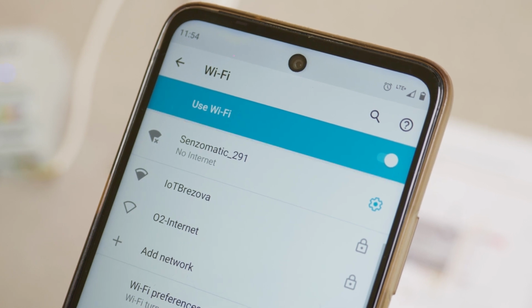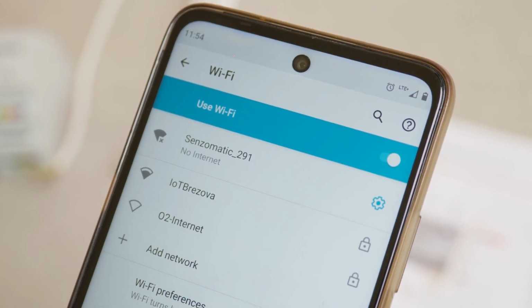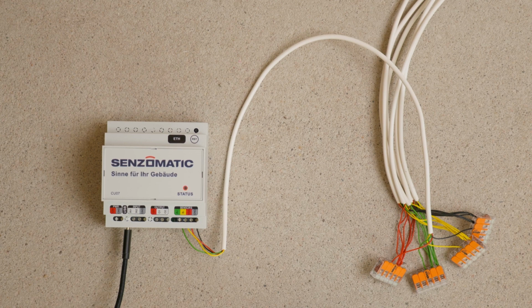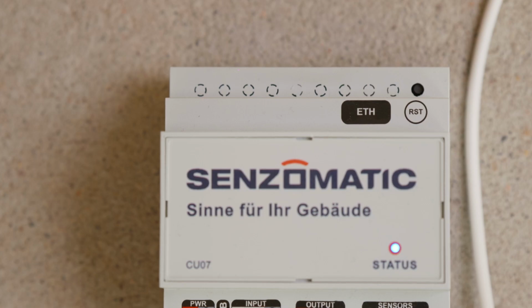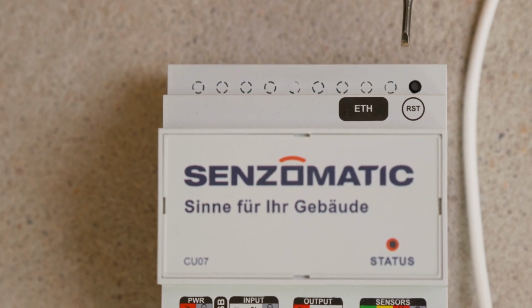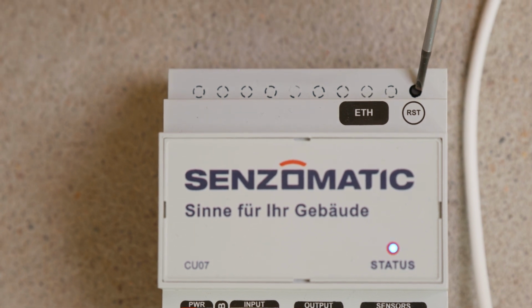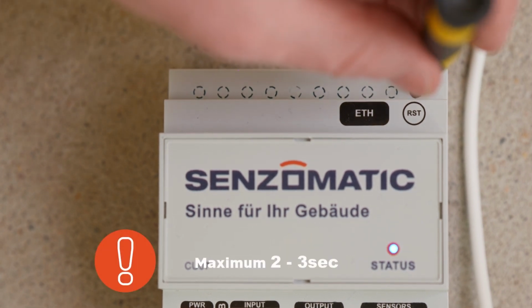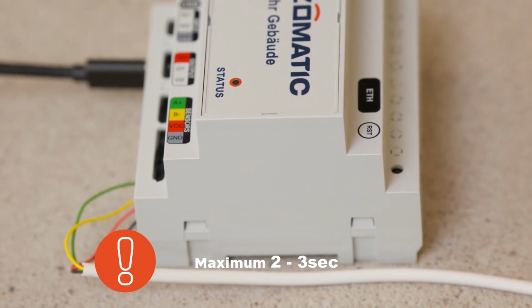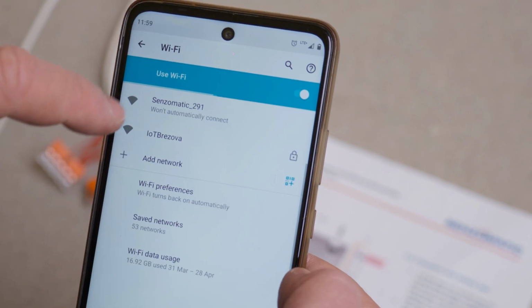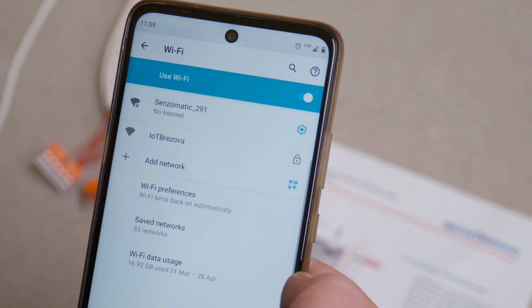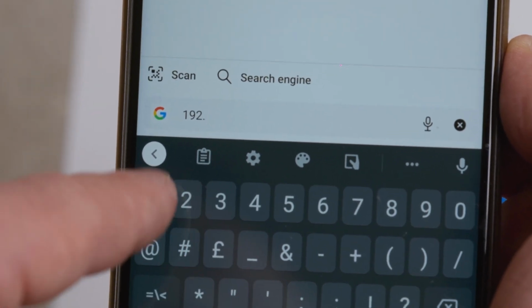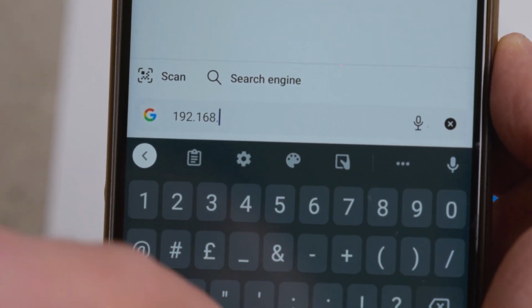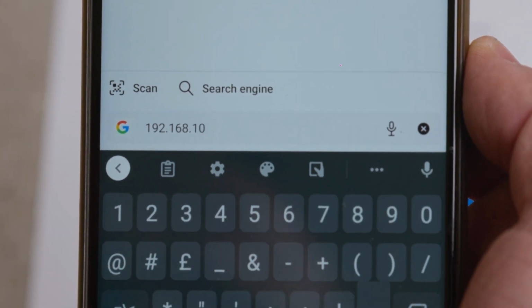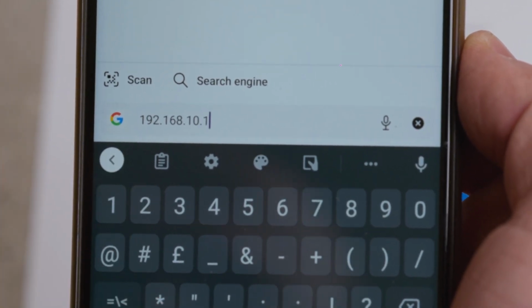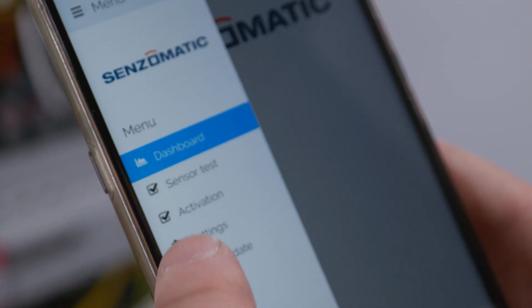Should you choose to activate the system without an internet connection, offline, connect to the unit in the same way as when performing the sensor test. This means turning the unit on, then pressing the RST button for 2 to 3 seconds to pair with the Wi-Fi network of Senzomatic, and entering the address 192.168.10.1 into the browser. Then select Activation from the menu.